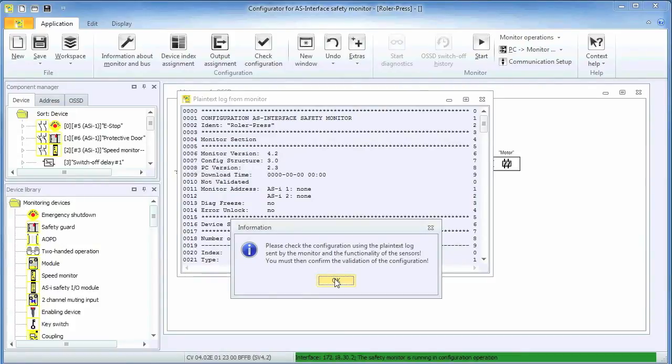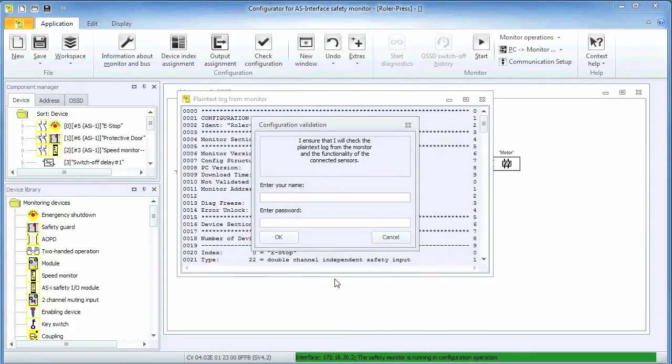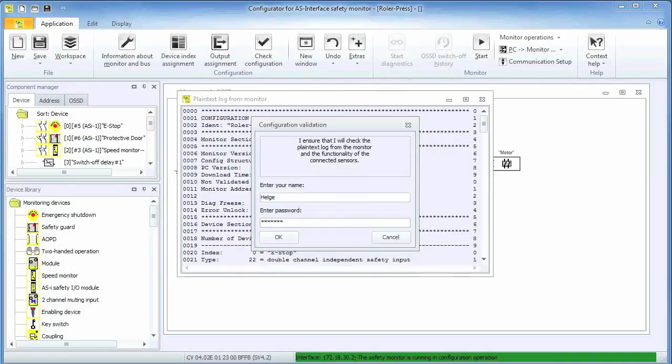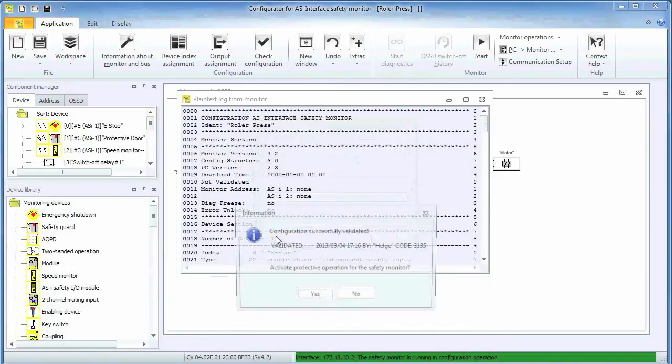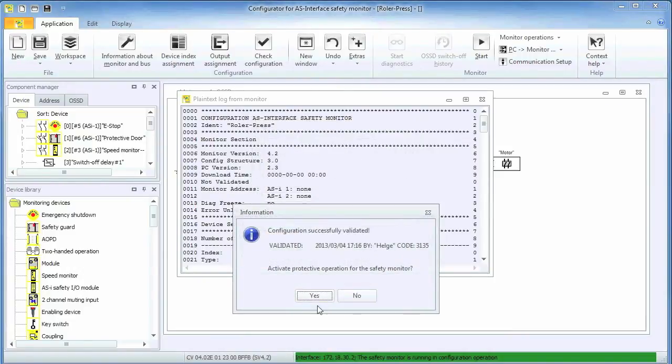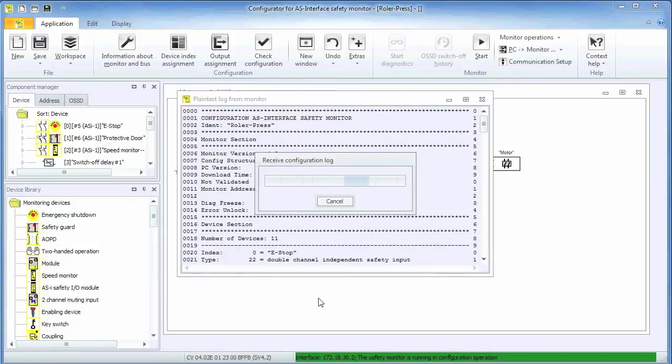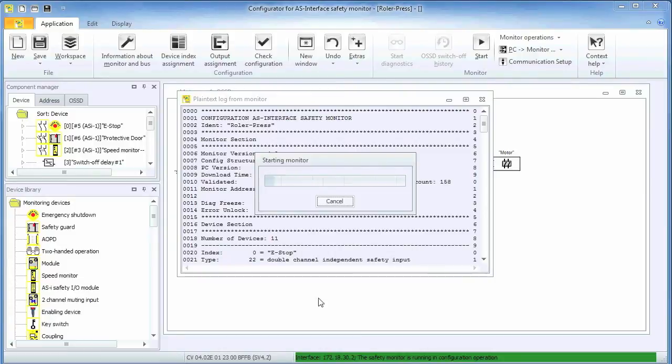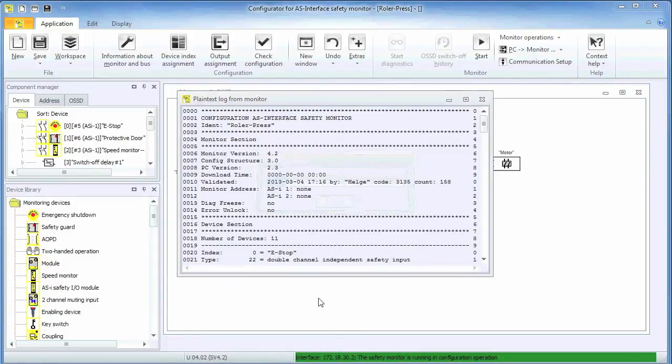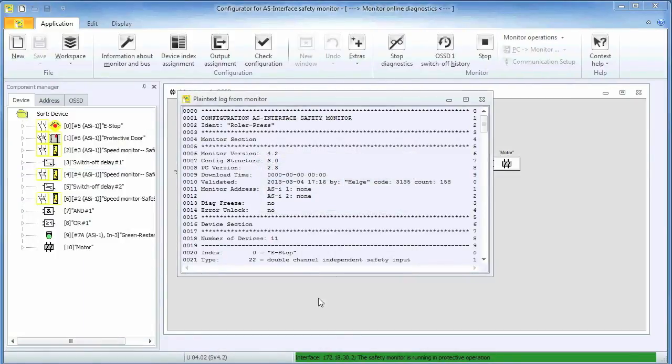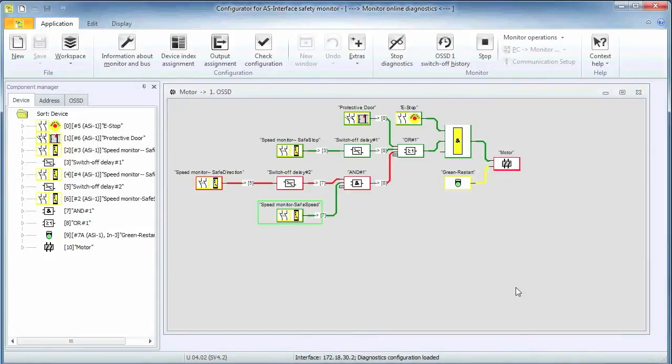As part of the validation step, the name of the validator along with a password must be entered. The name of the validator, a timestamp and a security code in addition to details about the configuration and all the modules on the network are stored in the safety controller. After signing off on the validation screen, the safety controller can be activated and that brings up the diagnostic screen.